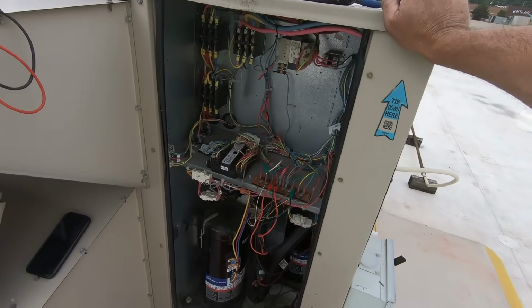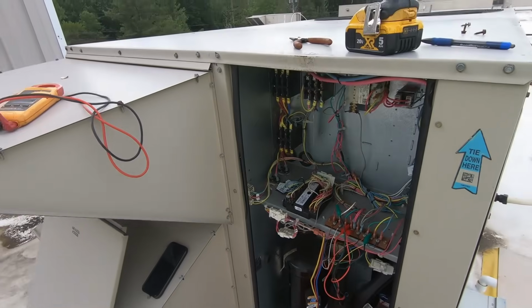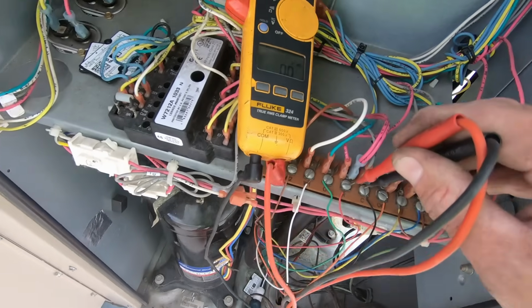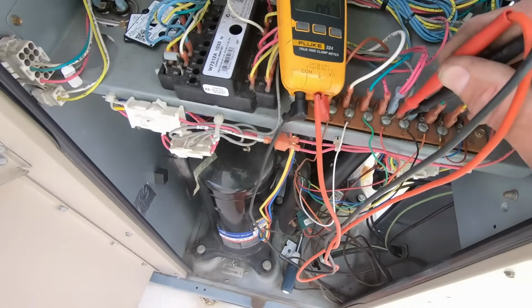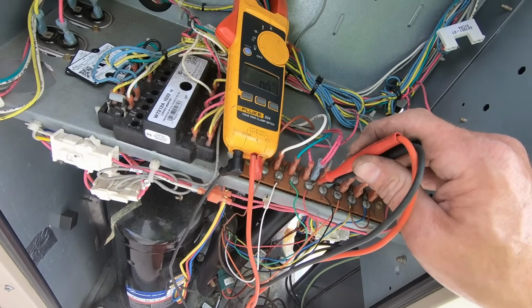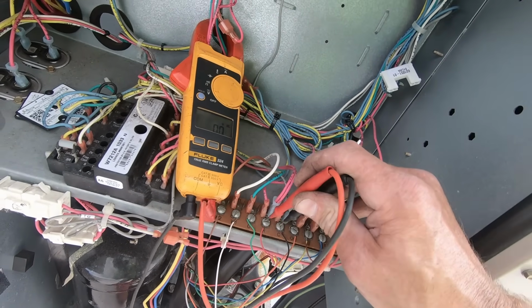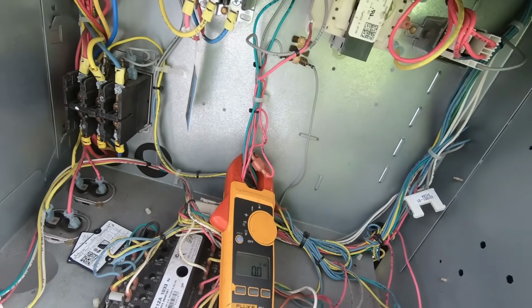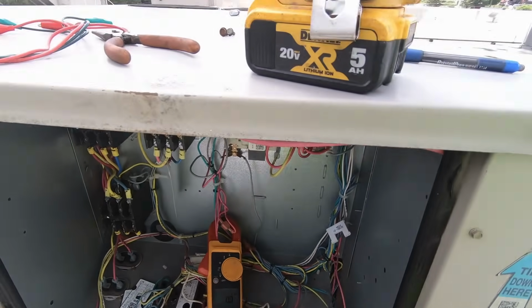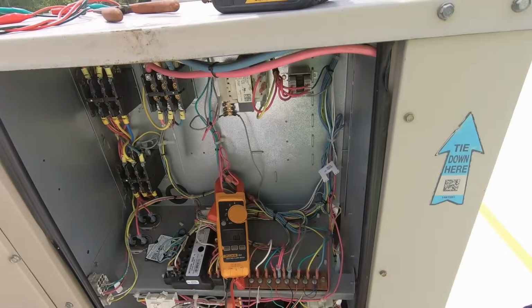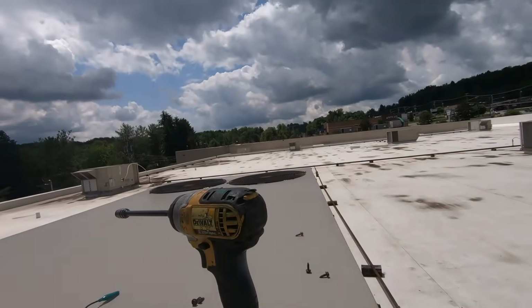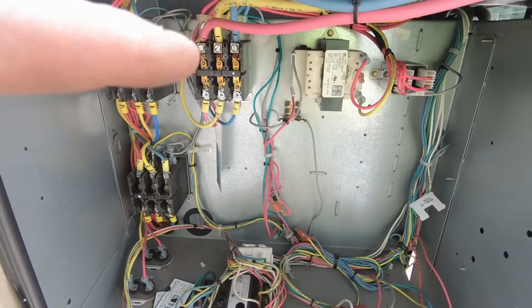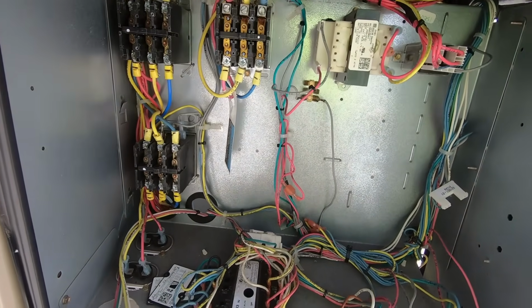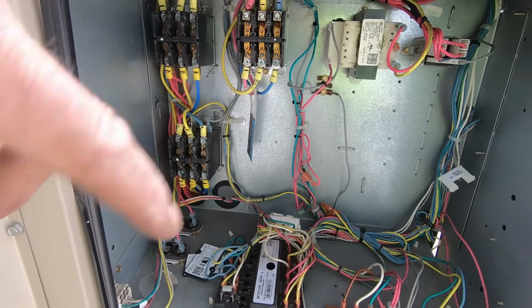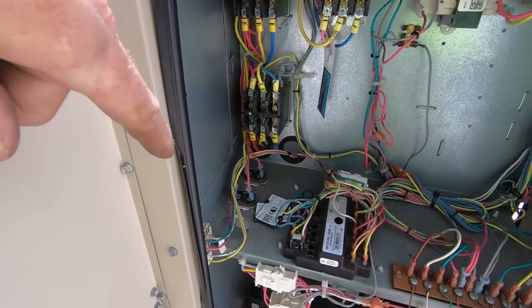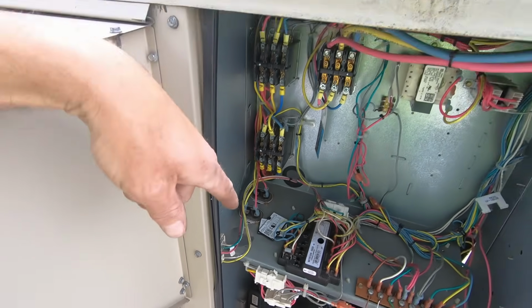Let me get my meter out. I'll be right back. Well, looks like the problem may just in fact be the transformer itself, because I'm getting 0 volts. I'm going to confirm that we have line voltage to the transformer, and if we do, then the transformer it is, and we move on. We do in fact have 208 to the transformer and no 24 volts coming out, so right there, bad transformer. We'll write that up. I'm going to test these capacitors on the condenser fan motors, and then I'm moving on.